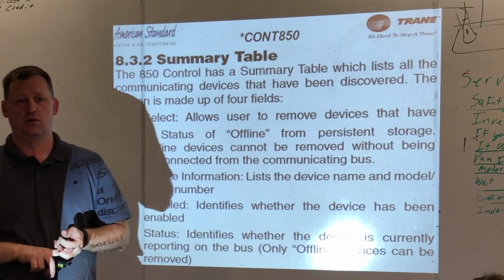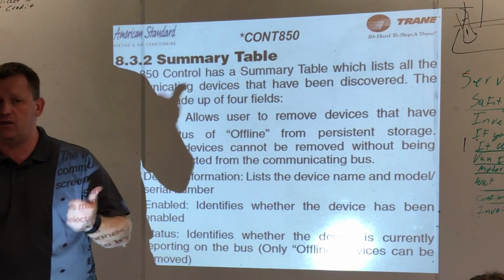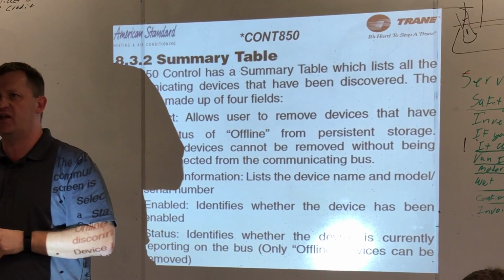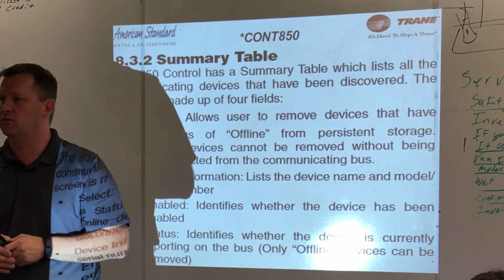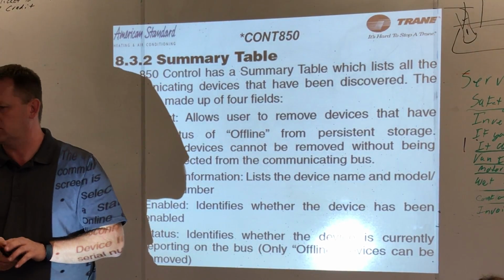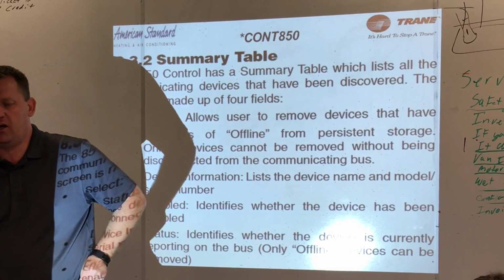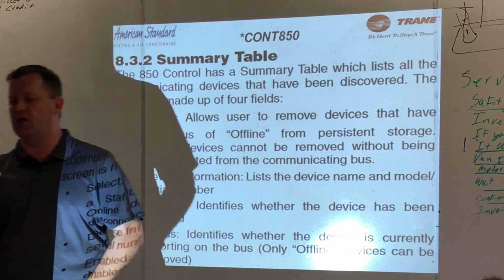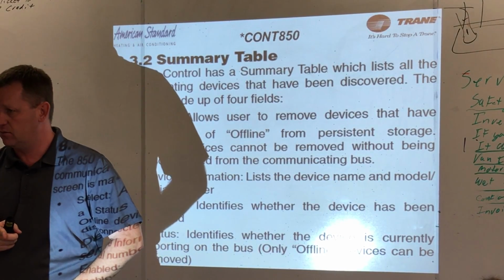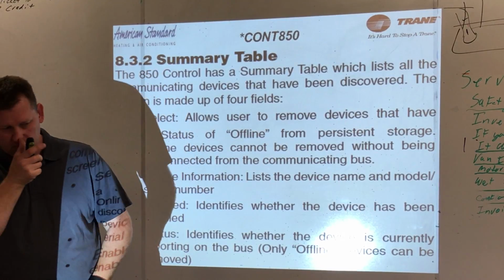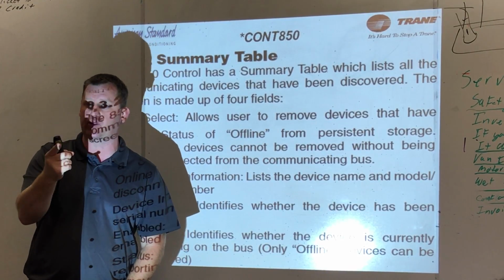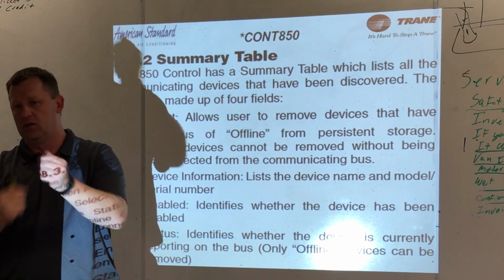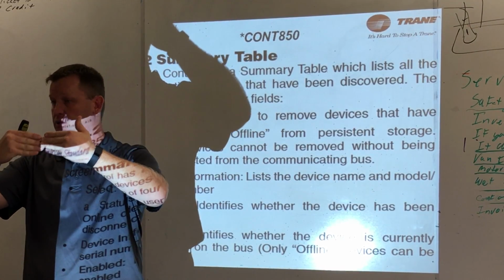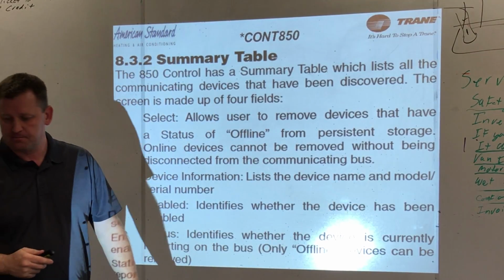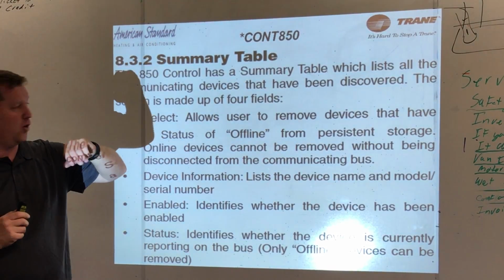Or a broken connection. So at the outdoor unit, if it's not connected to the indoor unit, you will get, I think it's like 16.7 volts DC right there. Roughly 16 volts. Okay. The relay panel or the communicating indoor unit is what creates the 12 volts DC. So that's where we're going to start checking voltages, either at the relay panels or at the stack. If we've got 0 volts, disconnect everything, check it again. Within about 10 seconds, if everything's disconnected, that voltage should come back up to 13 volts. So the relay panel and the indoor unit create the DC voltage.